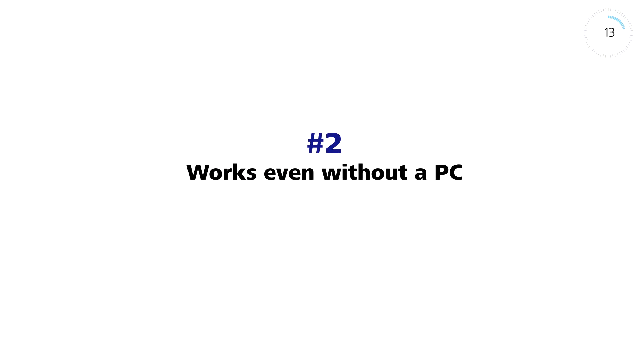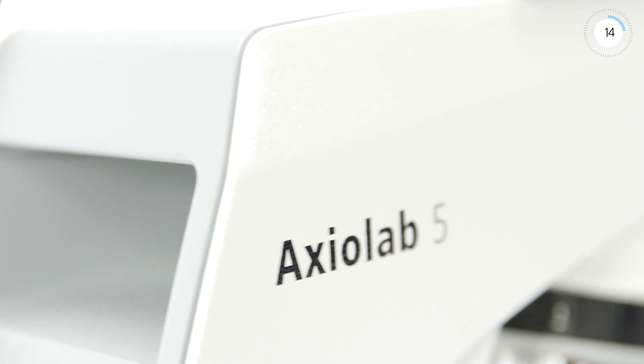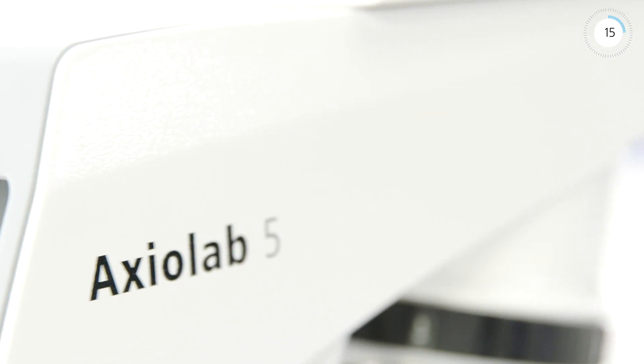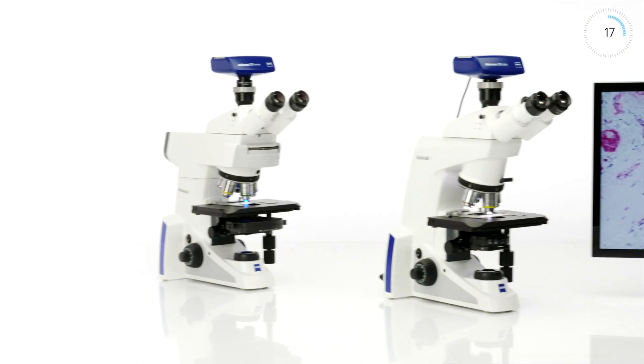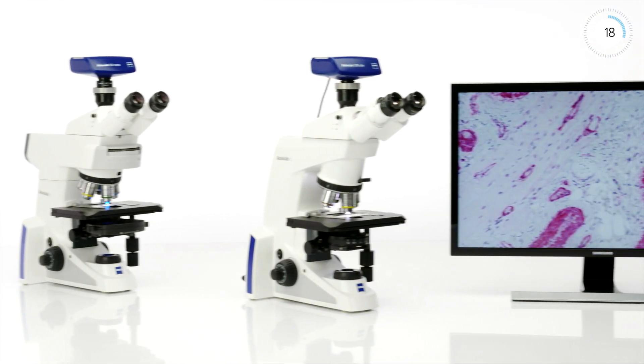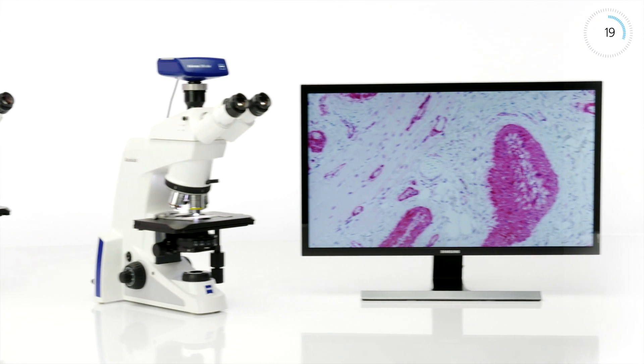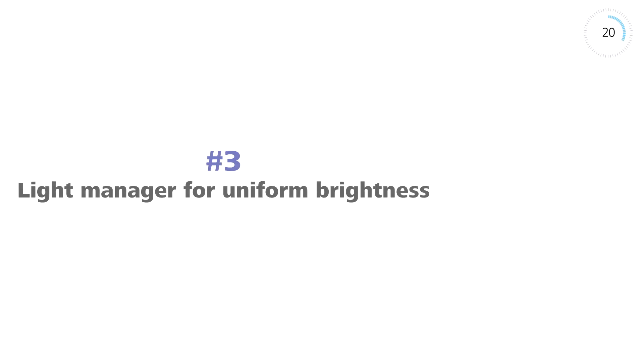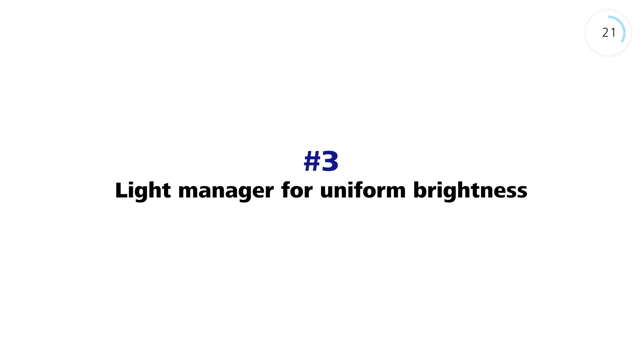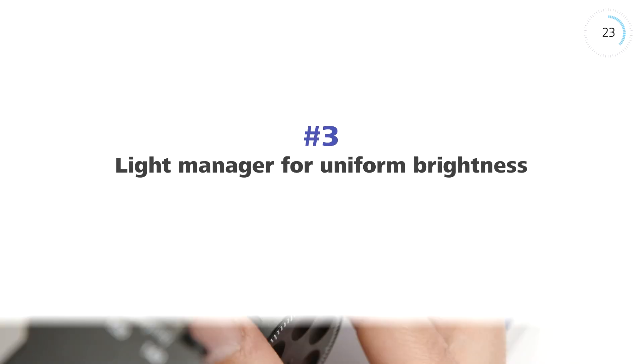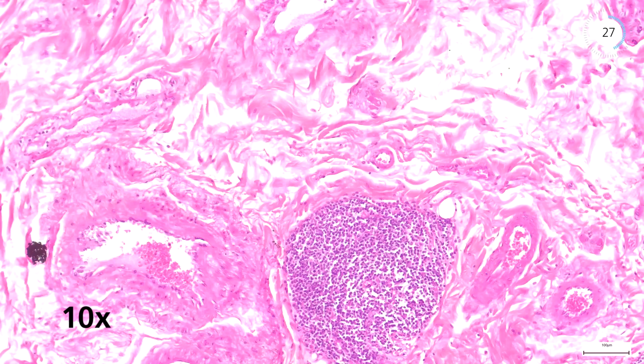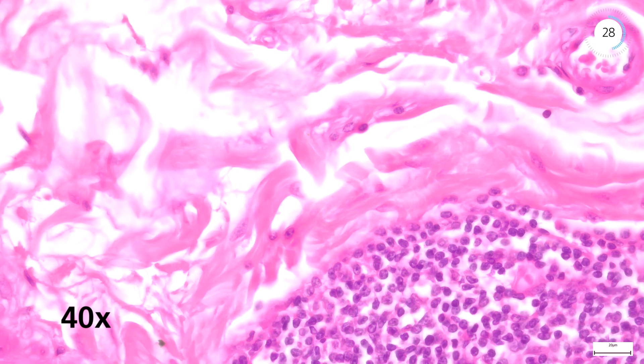This smart microscope system can be fully operated without a computer, which saves space, money, and prevents IT issues. The light manager memorizes the individually set light intensity per objective and provides uniform brightness at all magnifications.